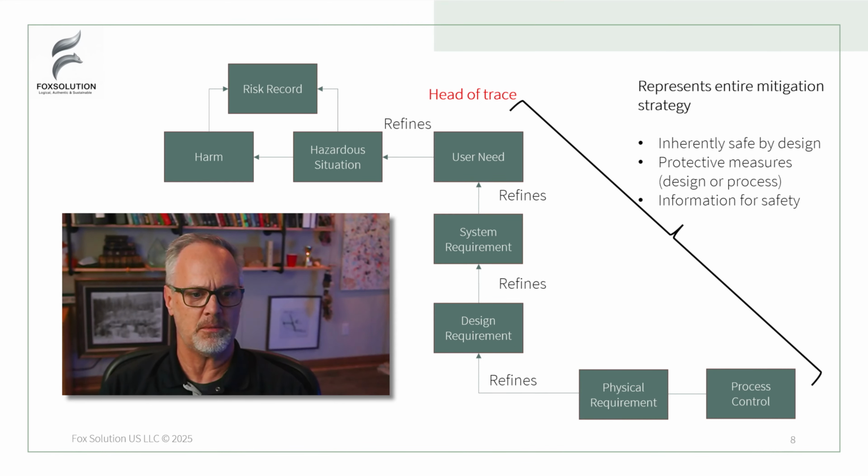So the mechanism by which that conductor becomes exposed: does it become exposed? What's the mechanism by which it does that? Those are the kinds of things that I can mitigate, but not so much the conversion factor. So then in the risk record, we're going to pair the P1 and the P2 to get P. And what P is, is how often the harm occurs.